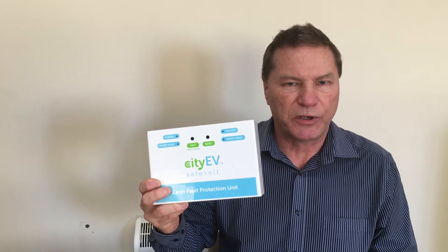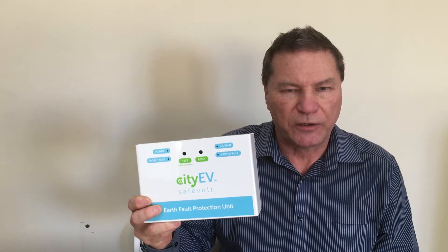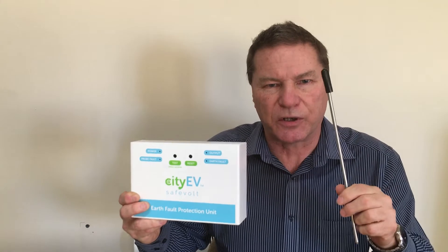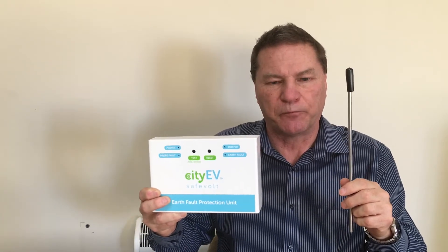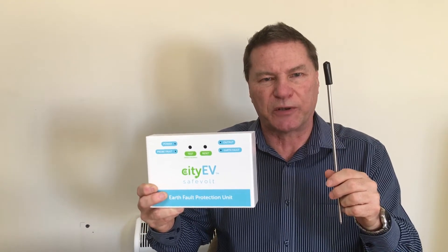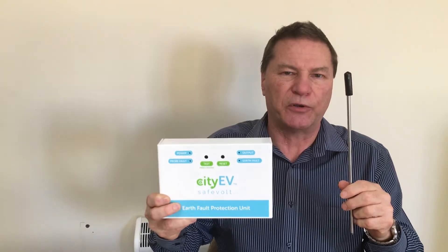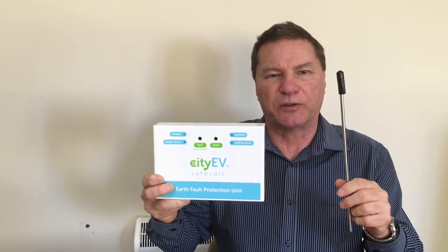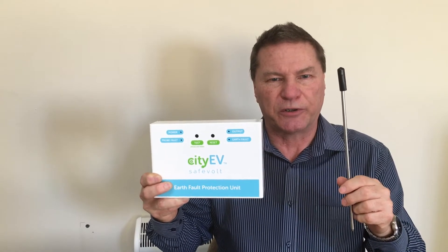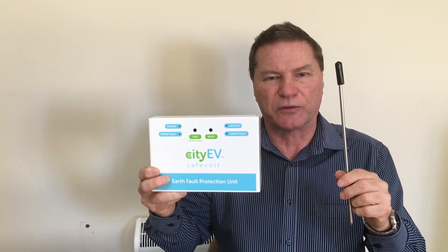The SafeVolt installs in series between the supply board and the charge point. It also has a small measurement probe which senses the voltage between true ground and the CPC connected to PME within the building. If at any time the potential difference rises above 70 volts, the SafeVolt unit will disconnect the live and CPC conductors from the charge point, rendering the installation safe in the event of a PEN conductor failure.